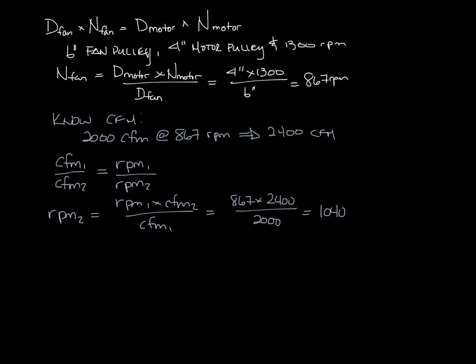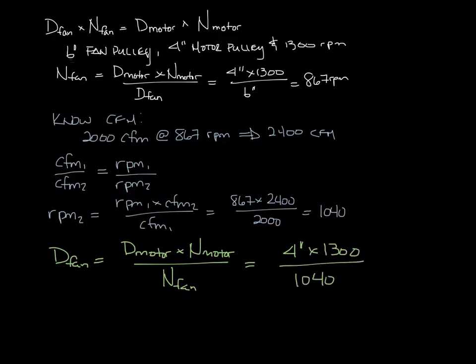So now we can go back to our equation for the pulleys, and the diameter of the fan is equal to the diameter of the motor times the RPM of the motor divided by the RPM of the fan. So that is 4 times 1300 divided by 1040, and that equals 5 inches. So a 5 inch diameter pulley on our fan system here would give us the 2400 CFM we're looking for.